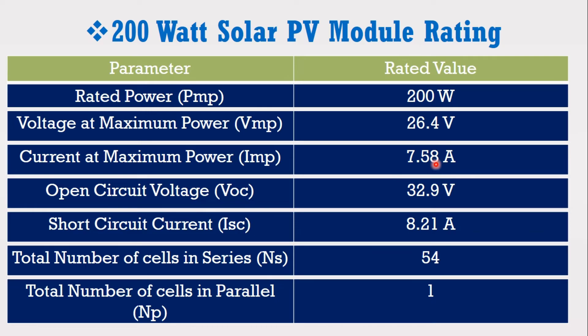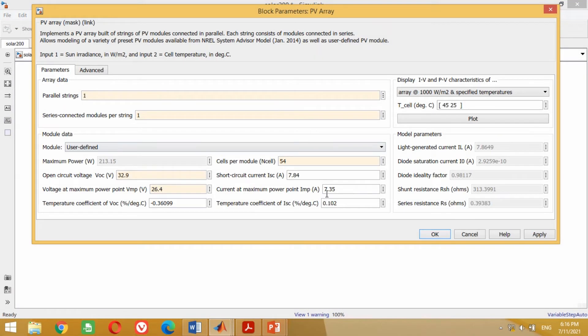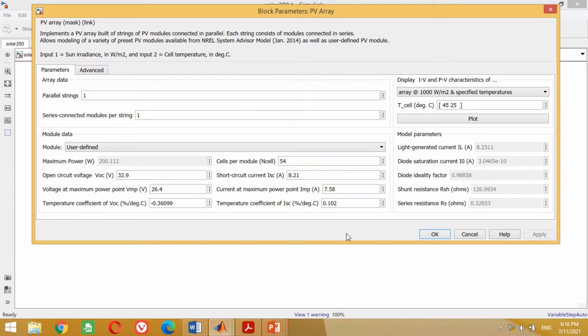The current at maximum power point is 7.58 ampere and short circuit current is 8.21 ampere respectively. Therefore, come to the model and write 8.21 for the short circuit current. At this stage, we have successfully inserted the data for the 200 watt solar PV module. Therefore, click on the Apply button in order to apply these values to the system.